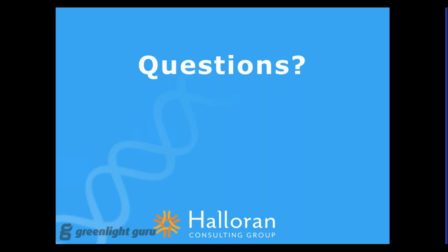So great question again. Like I mentioned before, I would see the FMEAs, the risk files, be something that was done during the design and development process and got filed away, and didn't get pulled out again until there was a major modification to the product or needed to be plagiarized for the next product that was being developed to build off of.